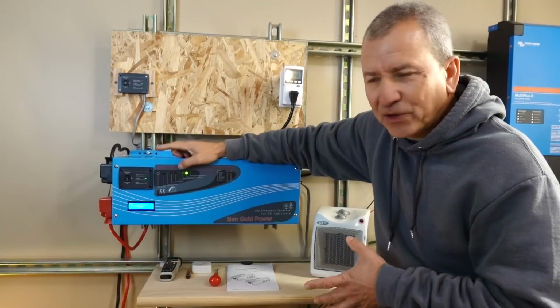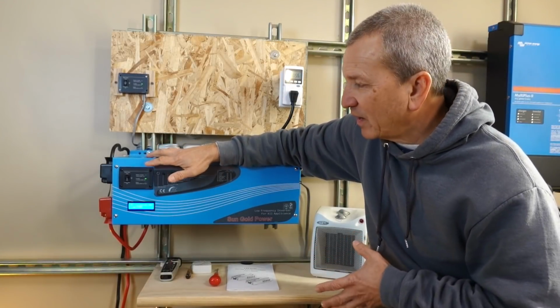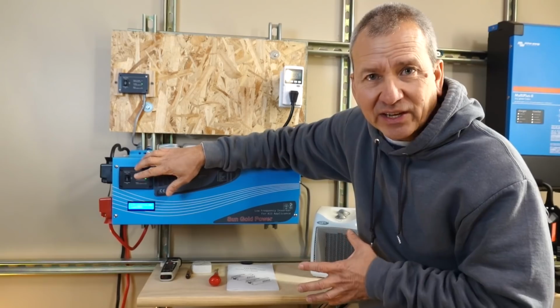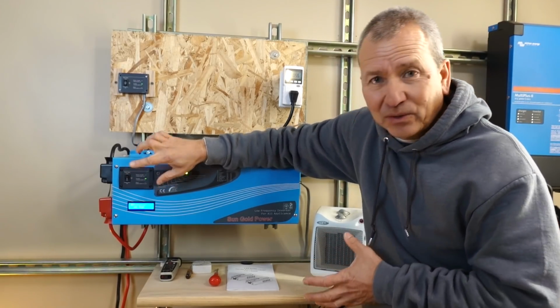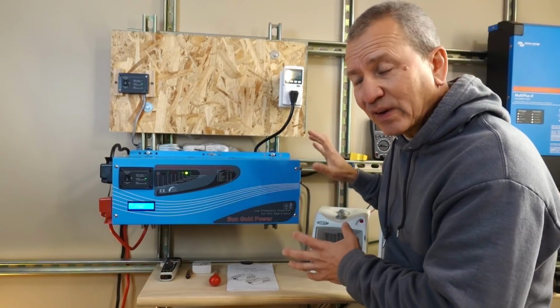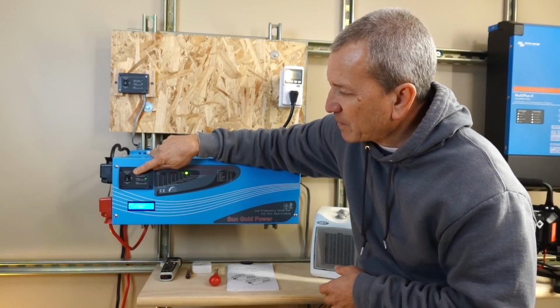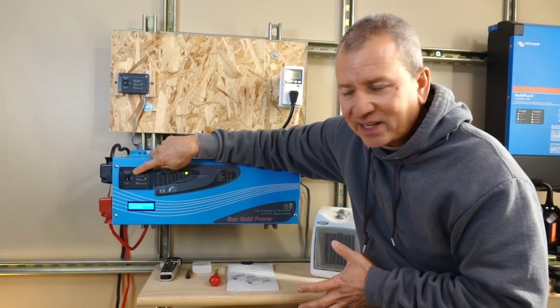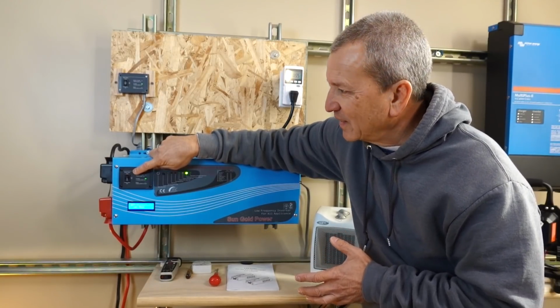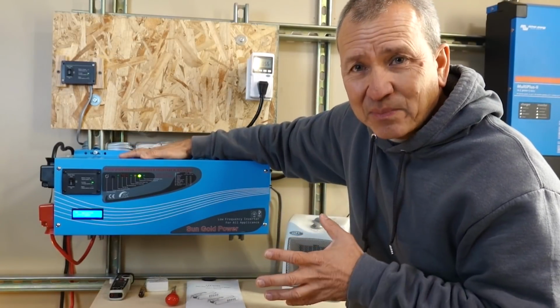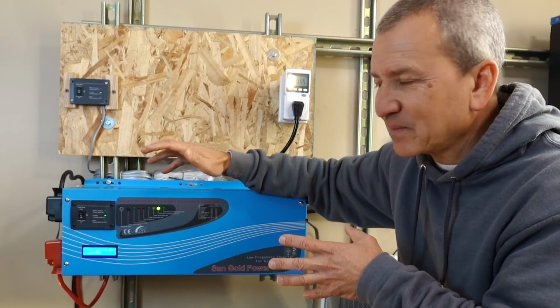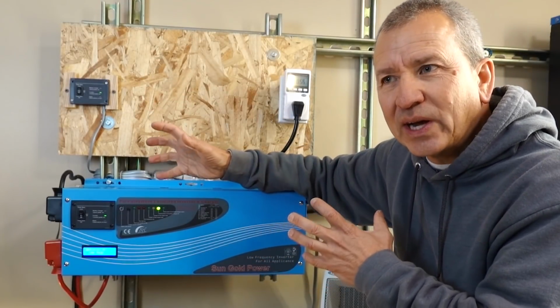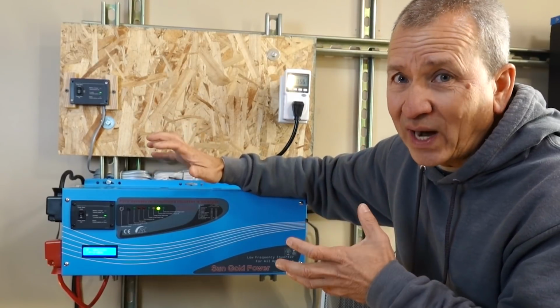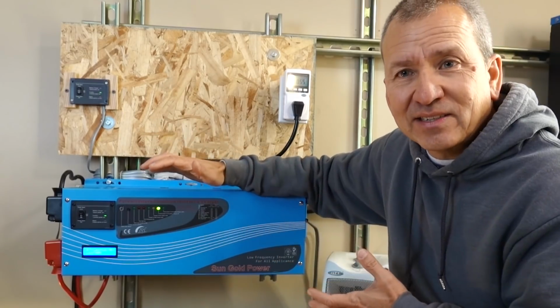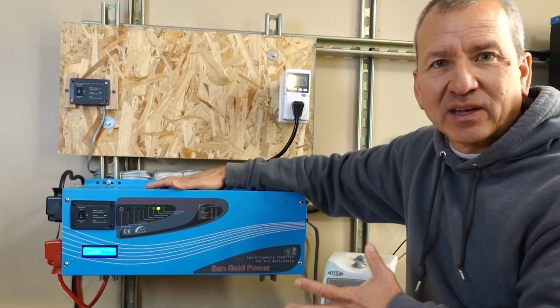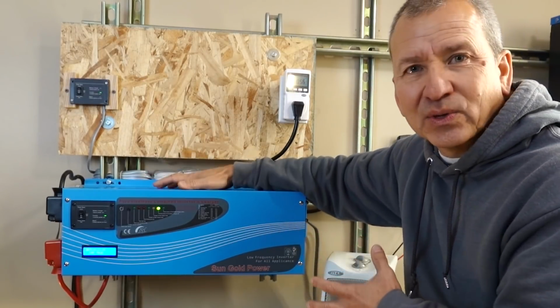So that's really good. Now the other runtime mode you select when you power the unit on, you have two options there. You have just the standard turn the inverter on mode, and it'll go into whatever priority mode you have it set up for. Or you can put it in this power saver mode. That's kind of interesting because what that does is it basically puts the inverter sort of to sleep. It shoots out a little signal every 3 seconds, and if it detects an AC load out there that's, I think, 24 watts or more, it'll say, oh hey, there's an AC load out there. I'm going to turn the inverter on, and then power those loads up to 100%.